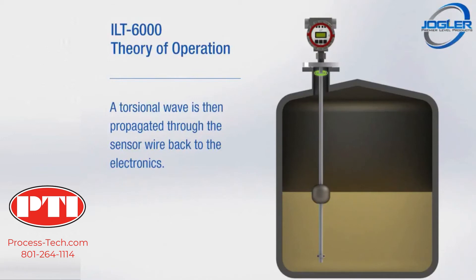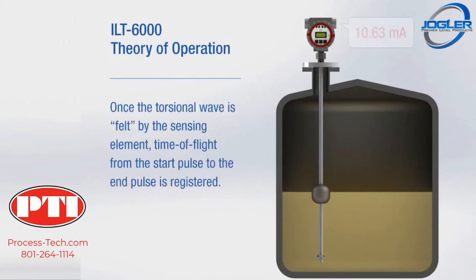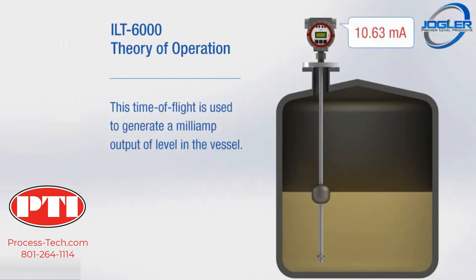Once the torsional wave is felt by the sensing element, time of flight from the start pulse to the end pulse is registered. This time of flight is used to generate a milliamp output of level in the vessel.